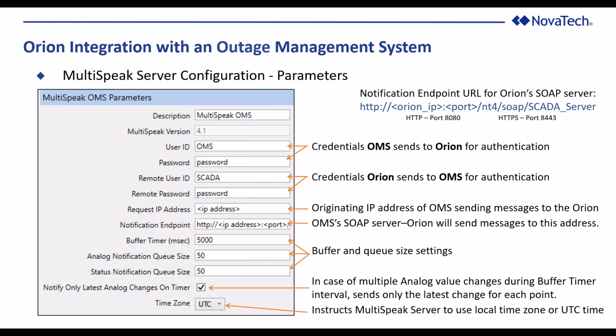As for the first user ID and password, to be clear, these are credentials that the OMS will send to the Orion. There's nothing additional you need to do other than populating these fields, because the NCD file going to the Orion tells it these are the proper user ID and password, so it checks that they match what the OMS sends. Vice versa, the remote user ID and password are the credentials the Orion sends to OMS. So on the OMS side, somewhere in setting up this multi-speak communication, you'll need to make sure this user ID and password are there, and as important, that they match.